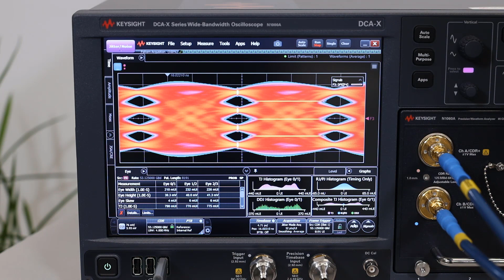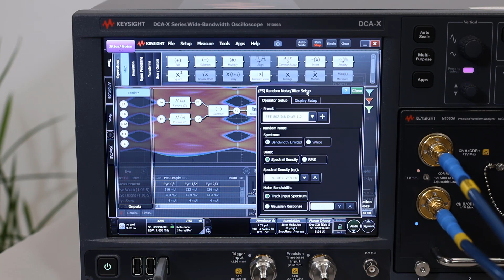Combined with the new FlexDCA software, it can fully support the IEEE 802.3CK measurements, such as the new CTLE definition with 2 gain stages, a 4-tap DFE with pulse response optimization, and it can also add a fixed amount of noise to emulate the receiver intrinsic noise.